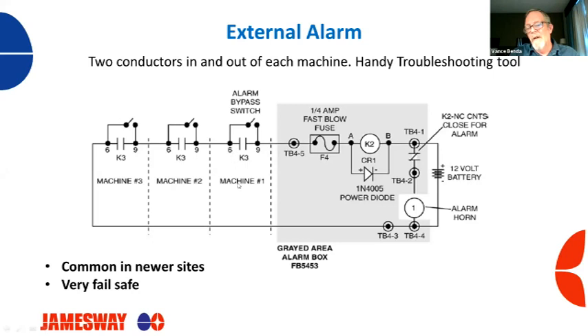And if a machine alarmed, it's going to send voltage only during alarm condition, latch this relay, which is going to close these contacts. So at that time, your battery is actually doing two things, latching this relay and blowing your horn. On the series system, your battery is going to be doing one of two things at any given time. It's either going to be latching this relay or blowing the horn, but it never does both at the same time.